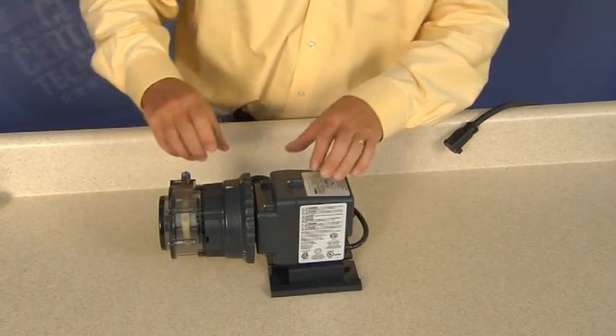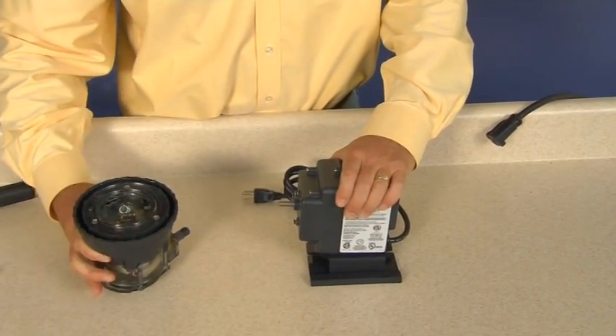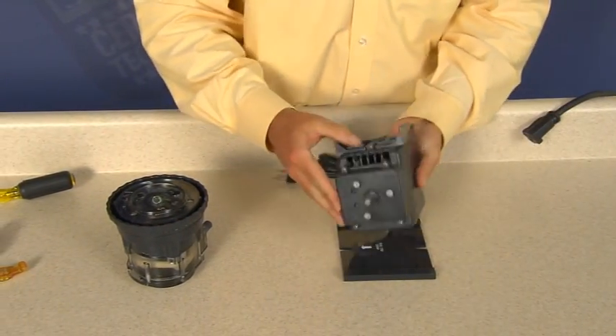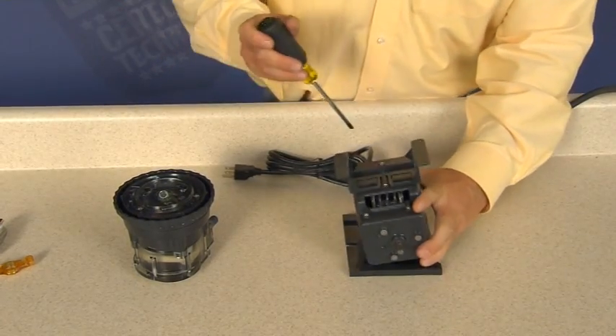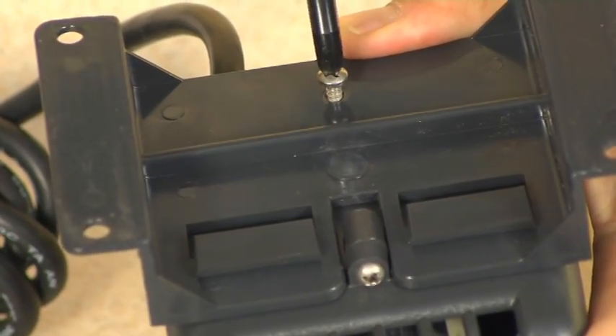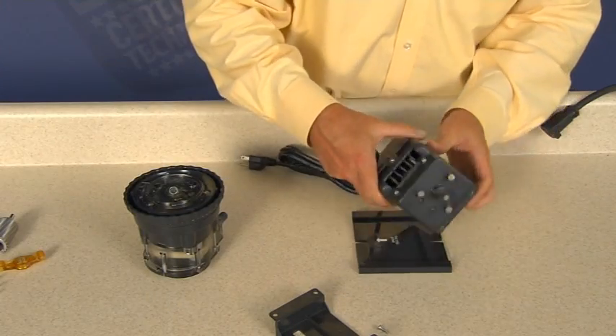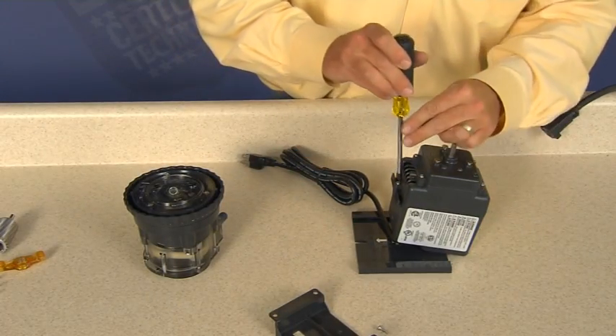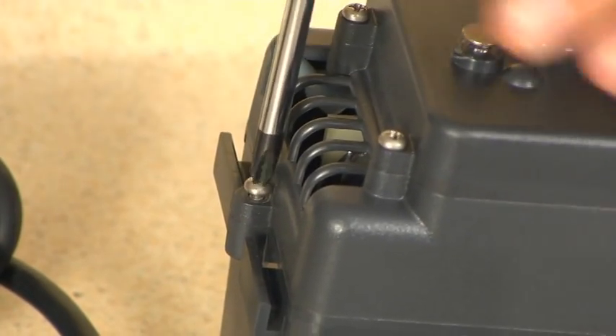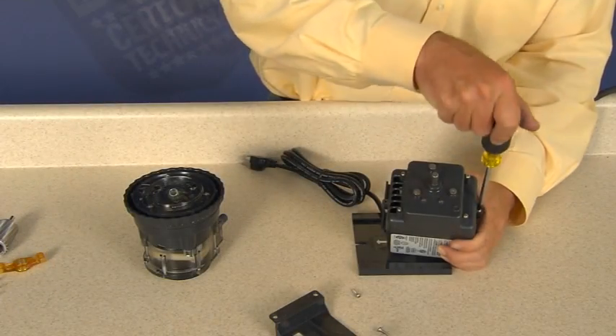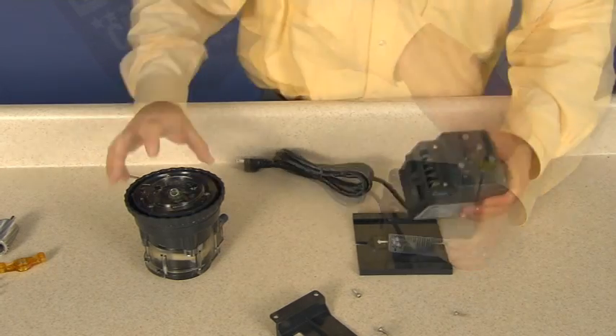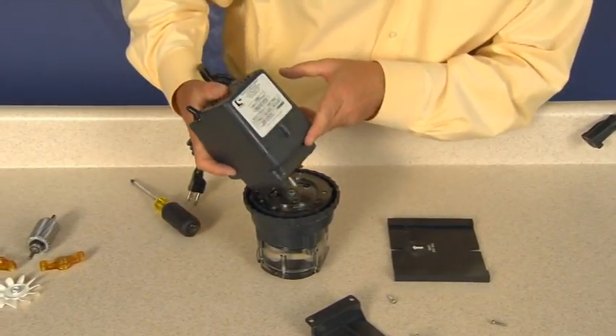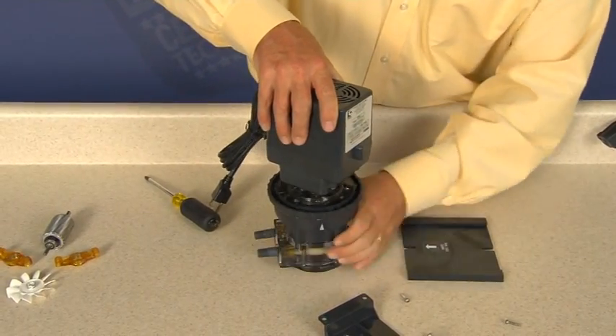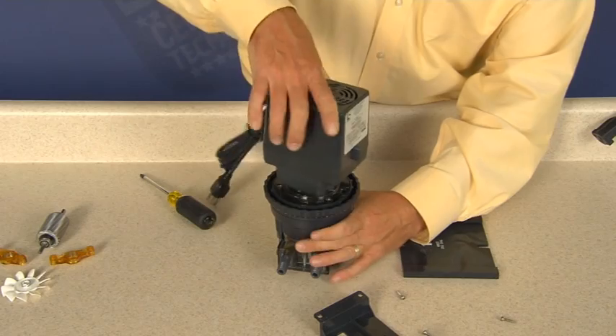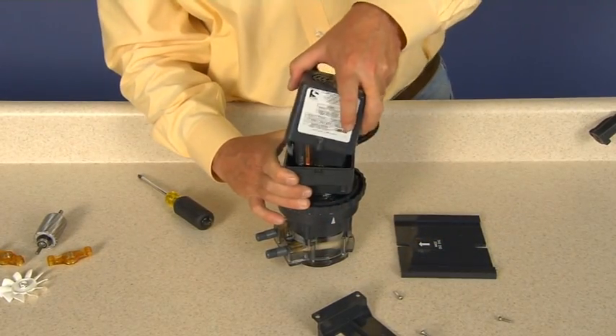Rotor assembly replacement. Disconnect power to the pump. Separate the feed rate control and pump head from the motor. Remove and set aside the motor base and screws. Remove and set aside two motor housing screws. Invert the pump and use the pump head and feed rate control as a stand to work on the motor. Remove the motor housing.